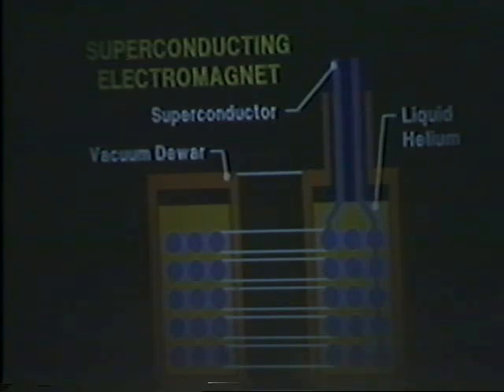Now, if we could replace the liquid helium by liquid nitrogen, several advantages would accrue. Next slide, please. The refrigerator would be cheaper and simpler. Most big systems will need a refrigerator, although it is possible to truck in the fluid. This would yield greater reliability. Nitrogen is readily available from the atmosphere and is very cheap compared to helium. And the problems with structural and support materials and the amount of insulation and so forth are greatly relaxed.